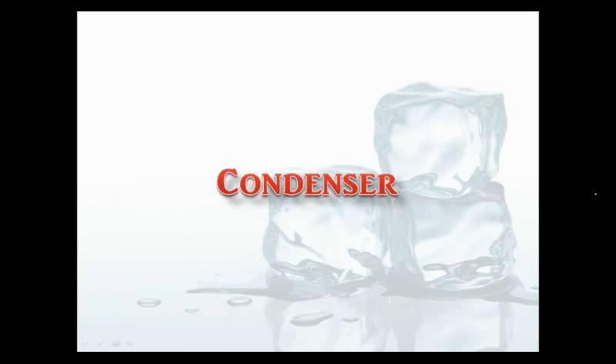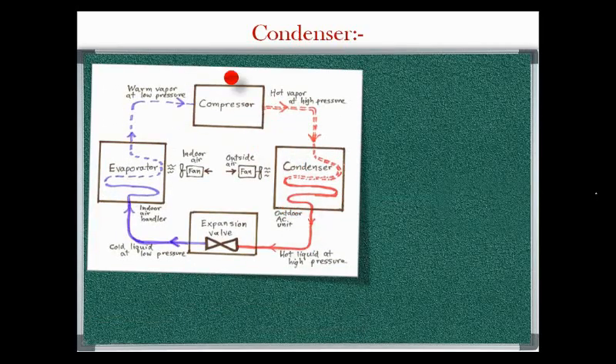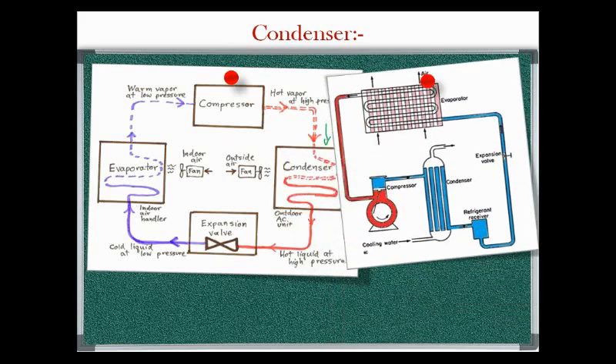The next topic after the compressor is the condenser. The refrigerant output from the compressor will be at high pressure and high temperature vapor state. This refrigerant then flows to the condenser. When the hot refrigerant vapor discharged from the compressor travels through the condenser, cool air or water flowing through the condenser coil absorbs enough heat from the vapor to cause it to condense. The cooling water flows through the condenser, and the gas condenses to a liquid giving off its heat to the outside air.